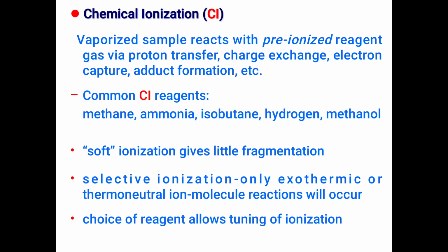Chemical ionization: the vaporized sample reacts with a pre-ionized reagent gas via proton transfer, charge exchange, electron capture, adduct formation, etc. The common CI reagents are methane, ammonia, isobutane, hydrogen, and methanol. Soft ionization gives little fragmentation.